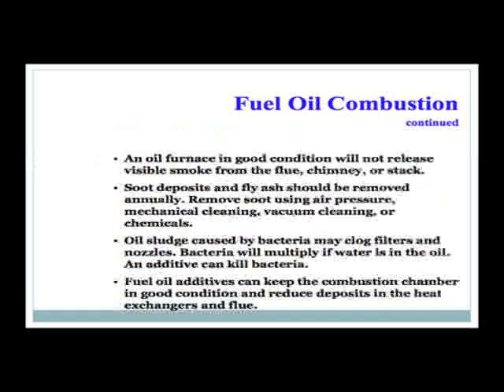An oil furnace in good condition will not release visible smoke from the flue, chimney, or stack. Soot deposits and fly ash should be removed annually using air pressure, mechanical cleaning, vacuum cleaning, or chemicals. Oil sludge caused by bacteria may clog filters and nozzles. Bacteria will multiply if there is water in the oil, but an additive can kill this bacteria. Fuel oil additives can keep the combustion chamber in good condition and reduce deposits in the heat exchangers and flue.